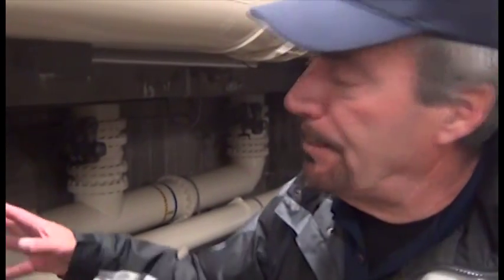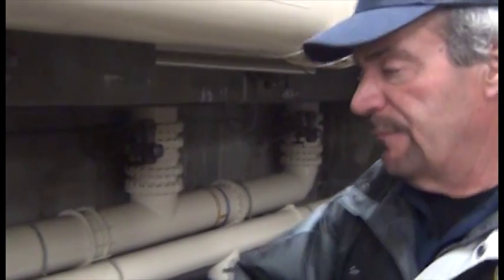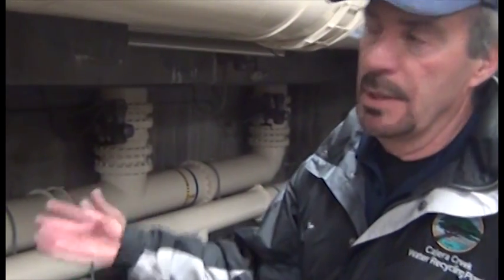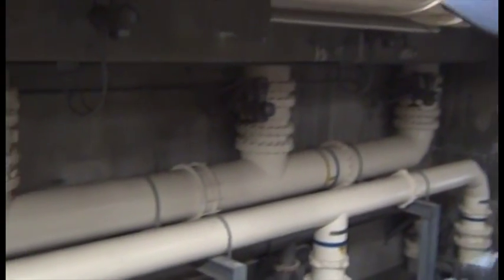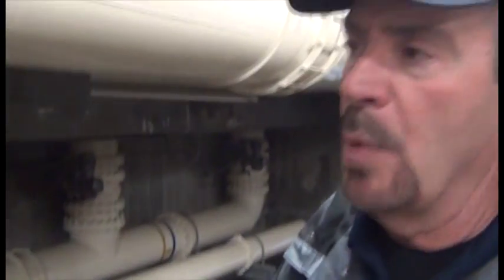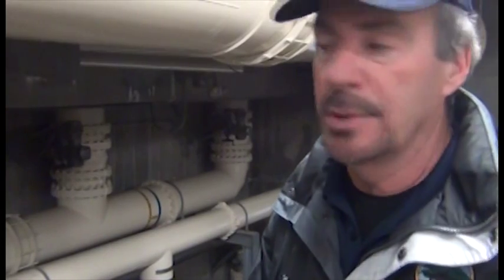Here we're looking at the piping system for the sand filter. As I mentioned, after running for about four to five days a sand filter needs to be backwashed. There's a very elaborate, fully automated valve system here, all computerized. In the middle of the night it picks two filters and runs clean water back through each sand filter in the opposite direction, dislodging all the trapped material into a tank, which then pumps it up to the start of the treatment plant for retreatment. All these valves have motorized actuators so the computer can open and close whichever valves are needed. In one backwash cycle, the computer will open and close about ten different valves.